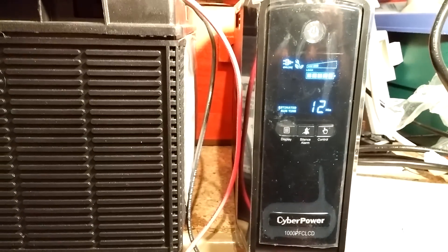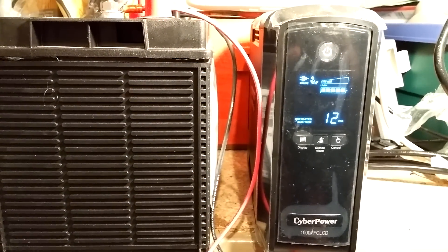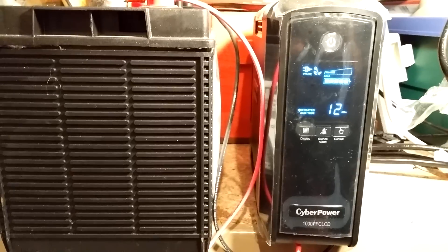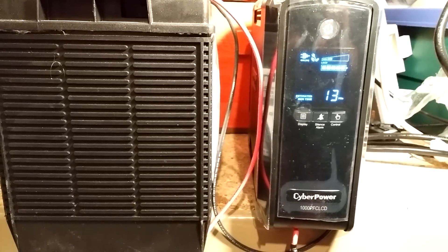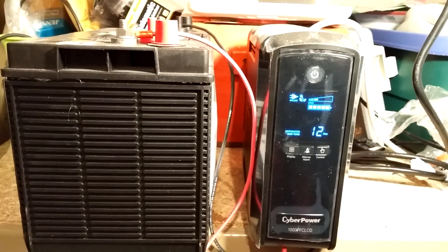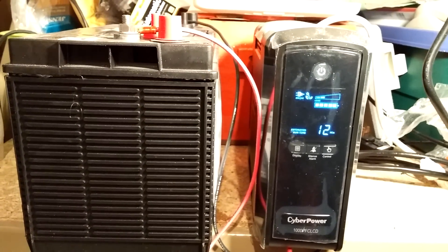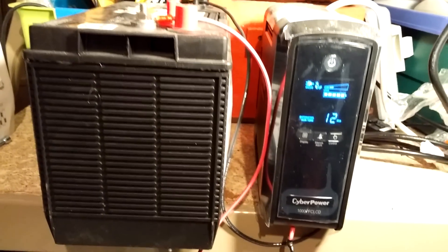The run time shows 12 minutes, but this thing will run for maybe a day based on the load I have on it at any given time. The UPS does not know that I have an external battery, so it can't calculate the exact run time for the unit based on this big battery.